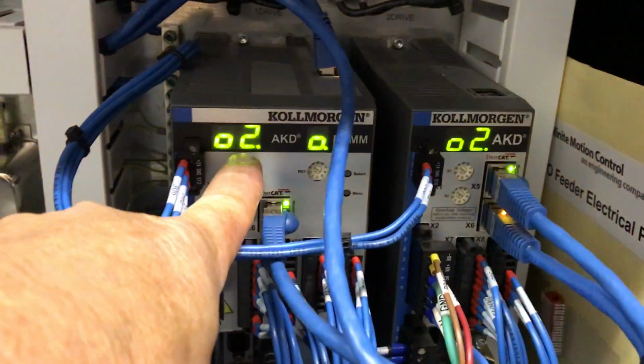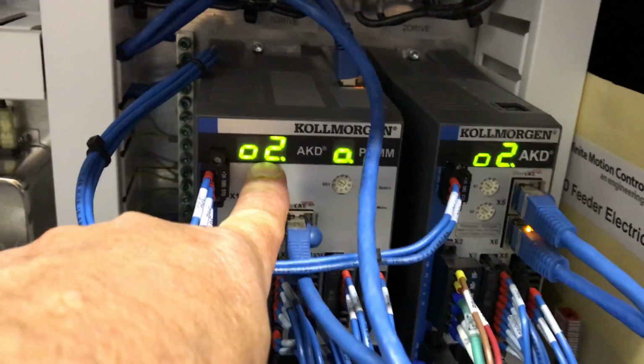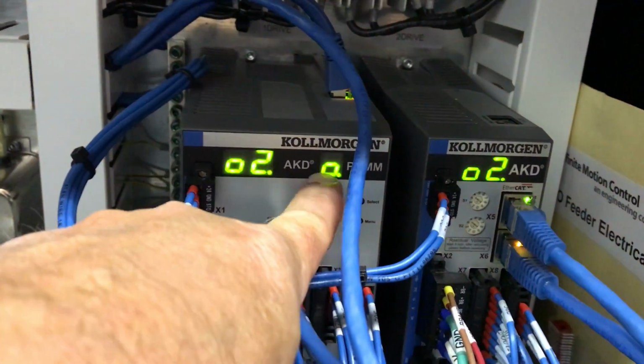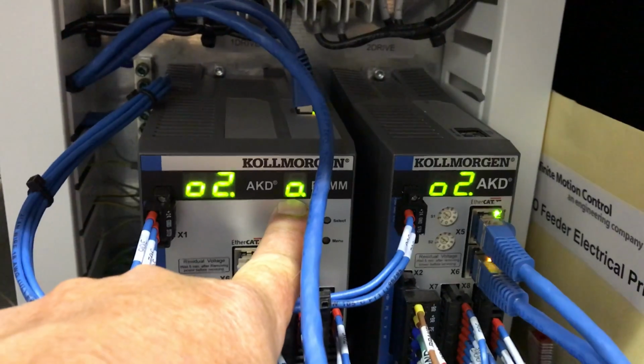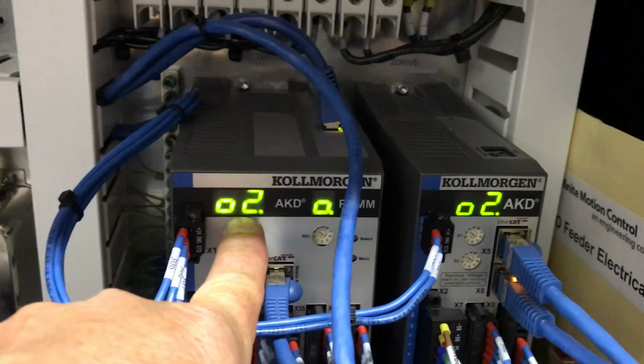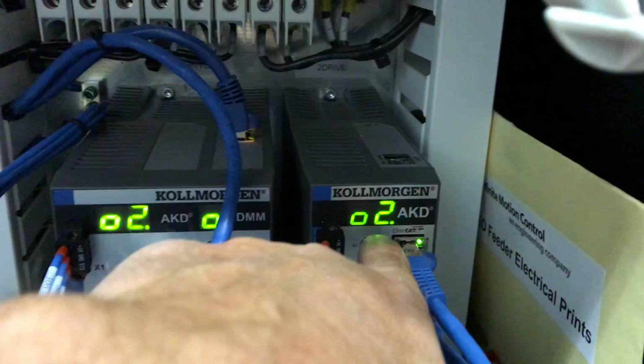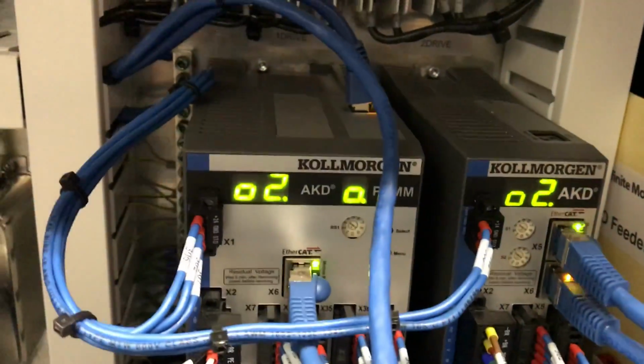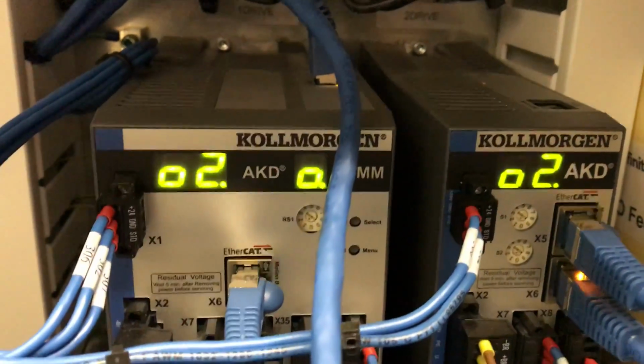Right now you can see there's two places to see codes here. This is the fault code window. This is the error code window. Also displays some additional information. Now right now we're seeing O2 and O2 on both drives. This means both drives are healthy and ready to operate.